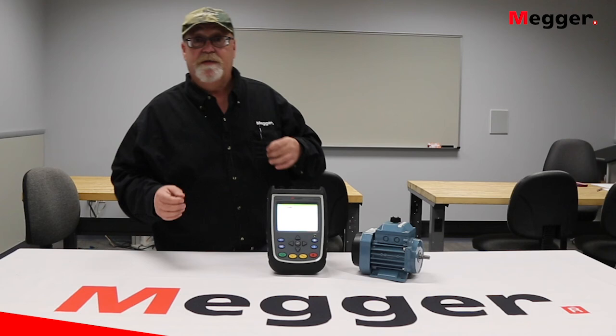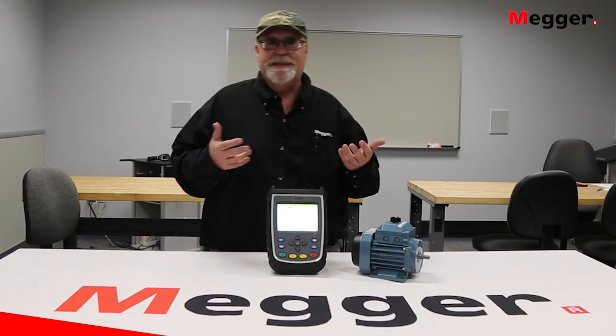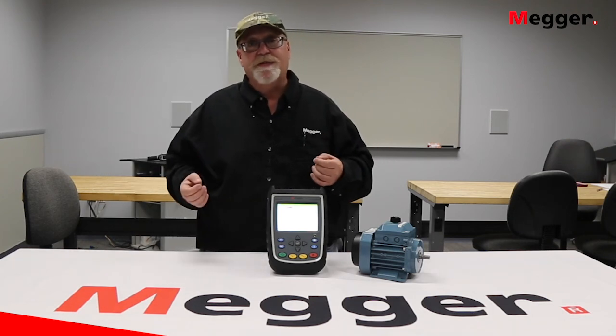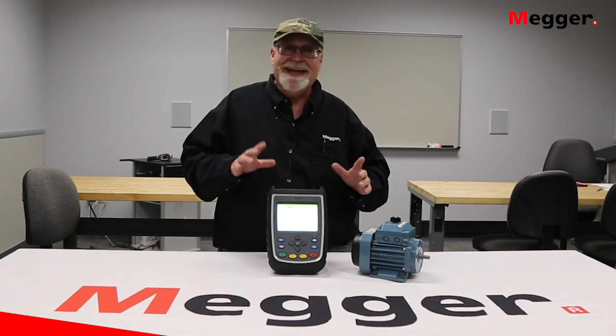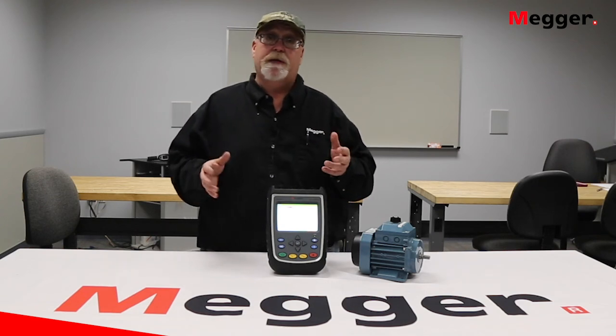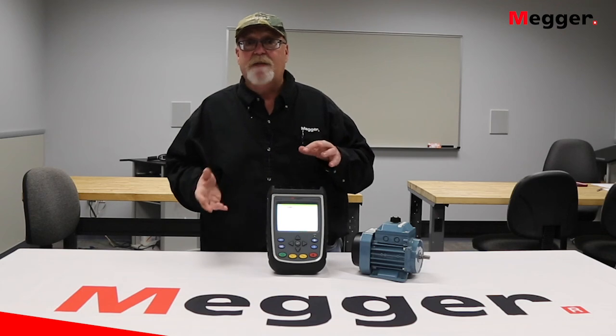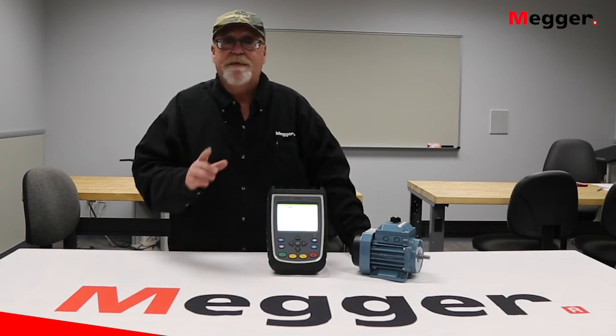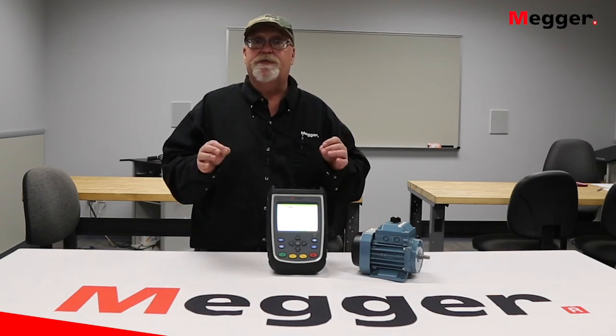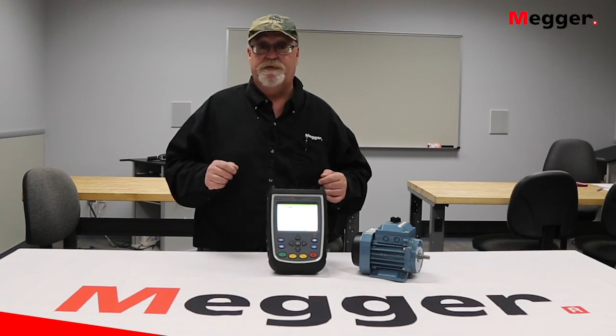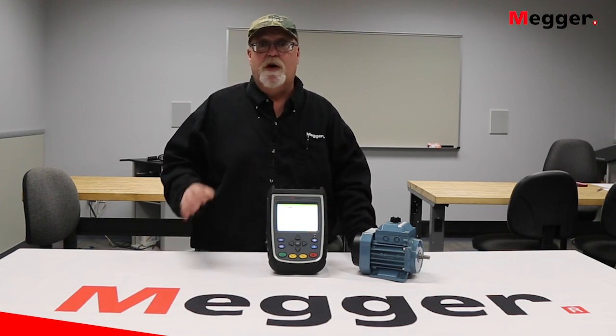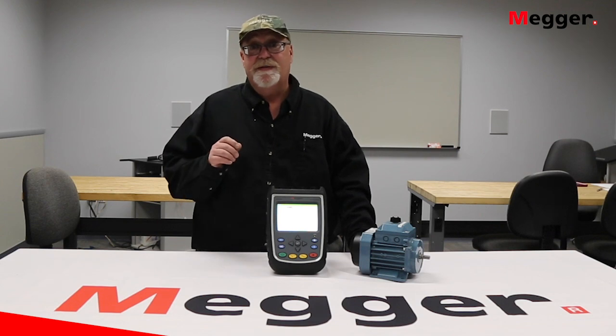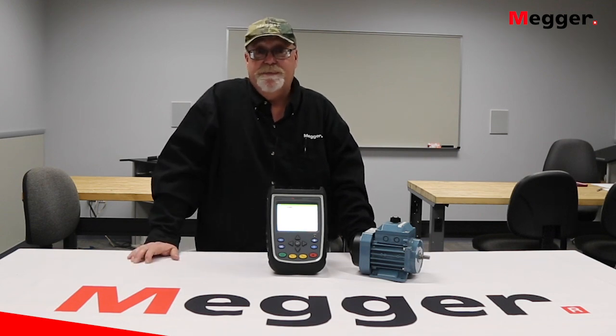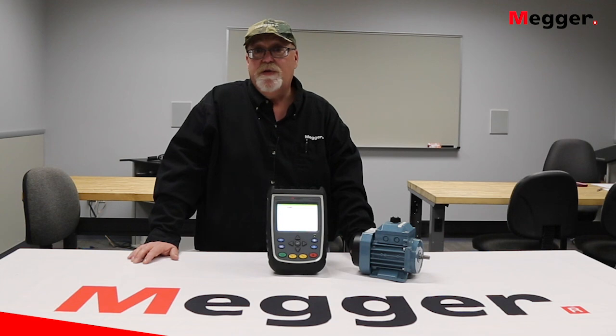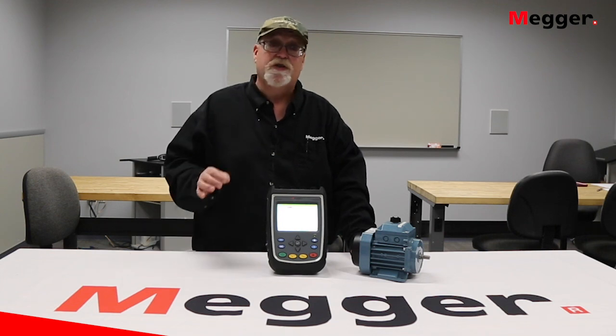And the installation of variable frequency drives, or VFDs, is rapidly increasing in industrial plants. Plant systems may not function properly with VFDs. Aside from potential harmonic issues, VFDs can react with the plant's electrical system and cause transient voltages. High-frequency transient overvoltages and voltage notching can cause equipment to malfunction. VFDs can also excite resonance and cause damaging overvoltages.